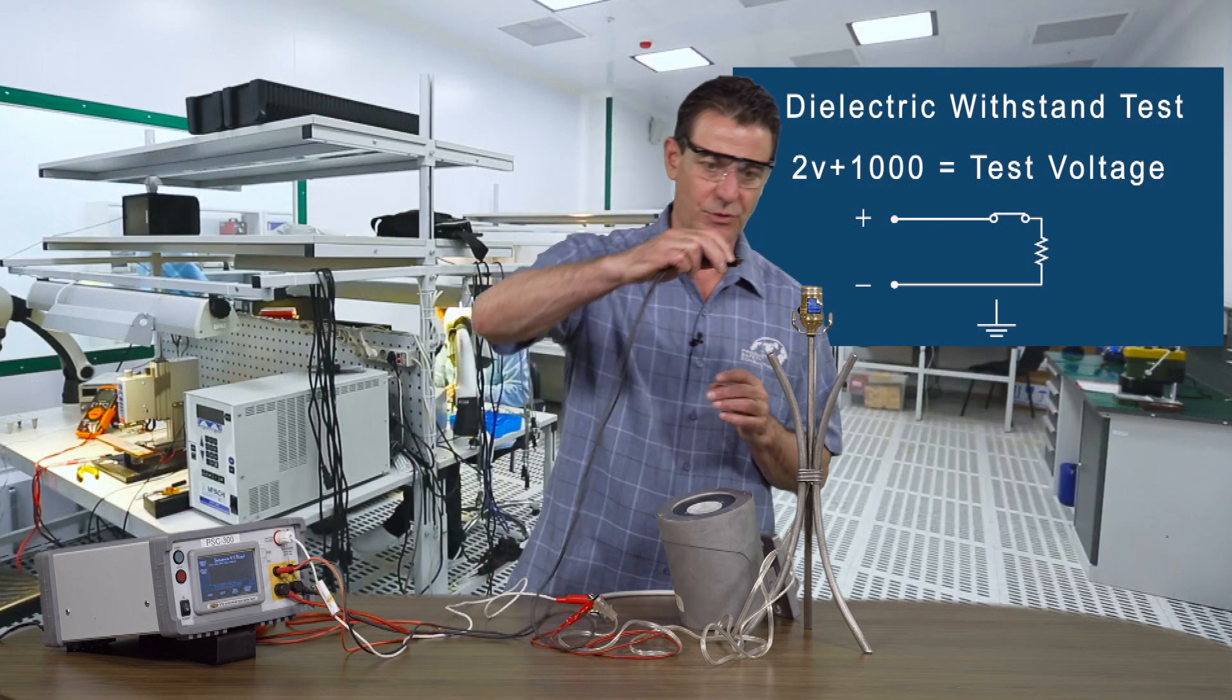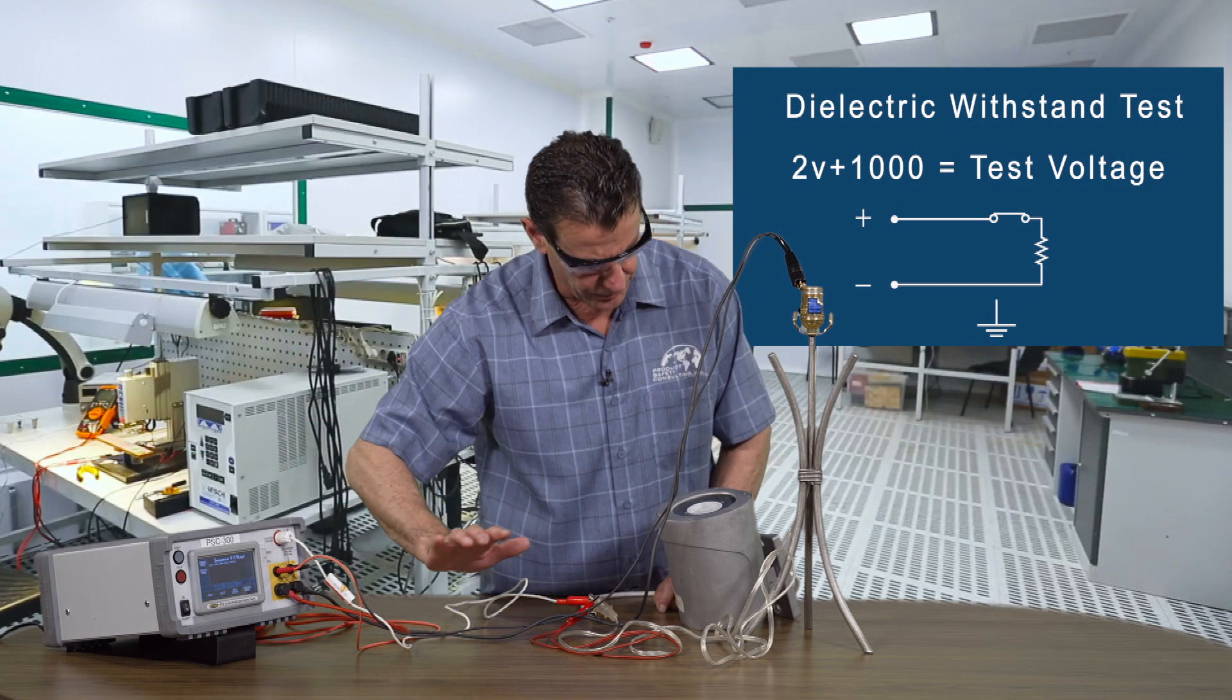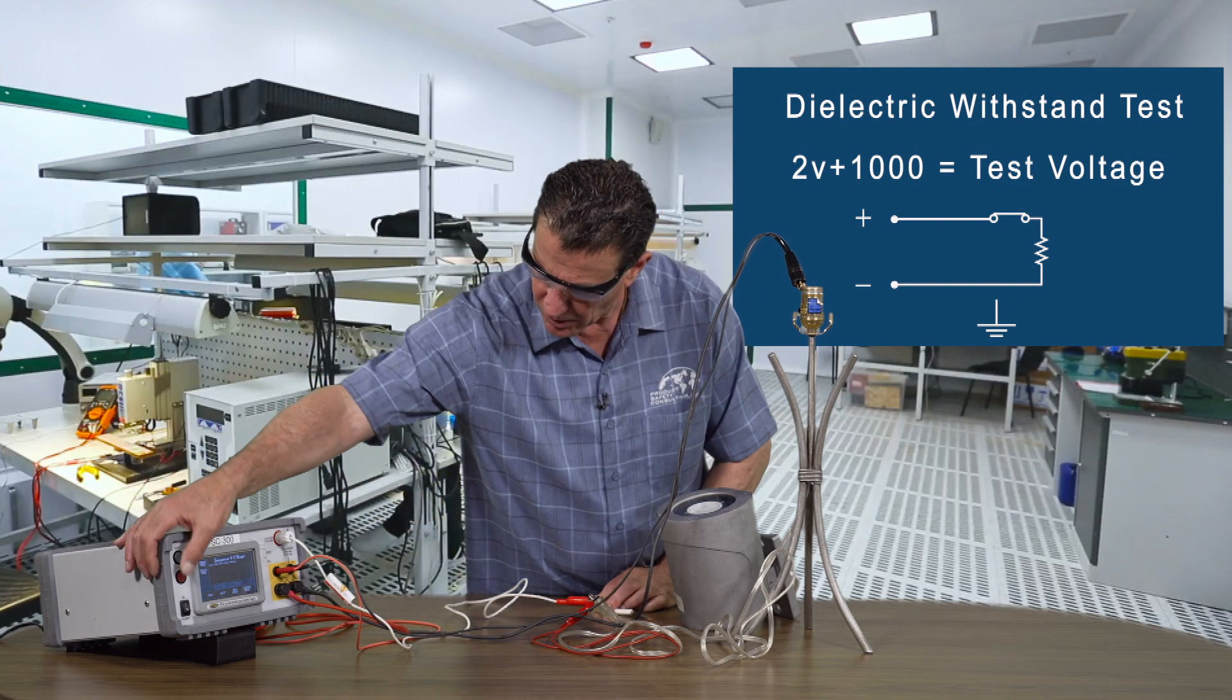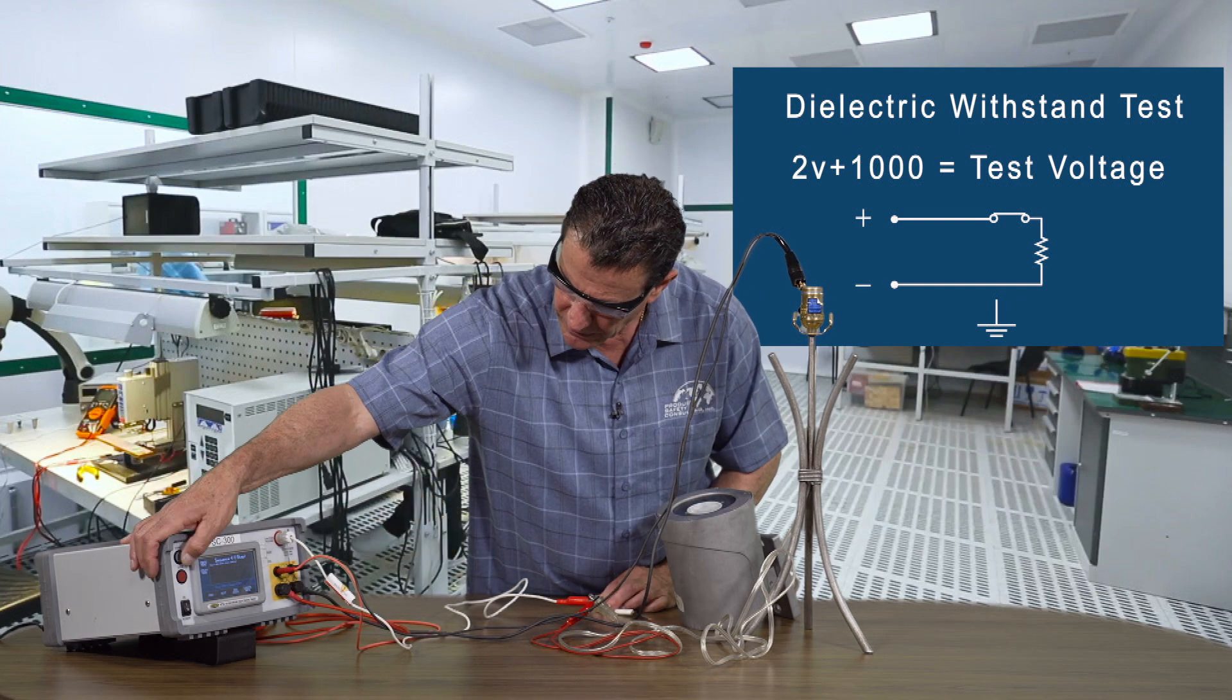Again it's 1200 volts. We're going to put our return lead on accessible dead metal and we make sure we're clean and good to go and we will start the test.